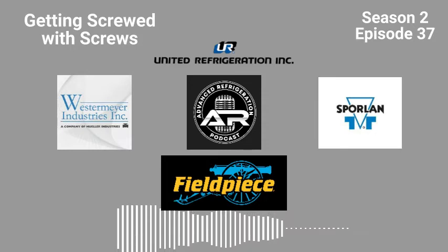Yeah, so these racks are all economized vapor injected scrolls or screws. So they have the economizer in there, and that's really important. That's your cooling for those compressors. They have economized vapor injection, or like Brett was talking, Bitzer uses that cool jet at times, or they use an economizer from a subcooler, or they also use Y10s usually to help cool them. But these are just economized injected because they have the oil coolers in them. They get away with that. But oil cooling with screws, if the oil is boiling hot, it's going to overheat your motors. It's going to overheat your rotors. It's going to dramatically decrease the life of the bearings in the compressor itself.